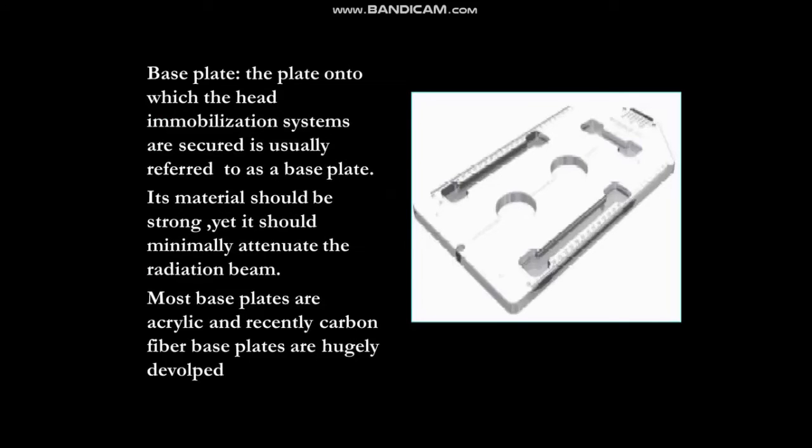Okay. Base plate: the plate onto which the head immobilization system is attached is usually referred to as a base plate. Its material should be strong, yet it should minimally attenuate the radiation beam. Most base plates are acrylic, and recently carbon fiber base plates have been highly developed.